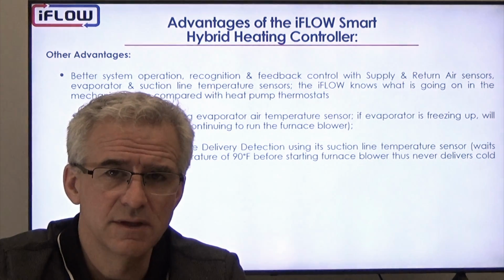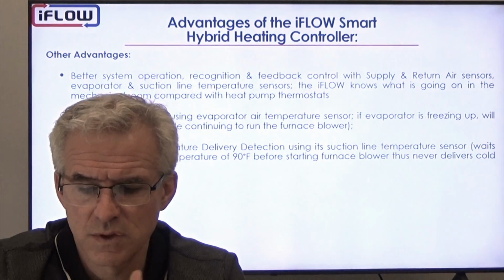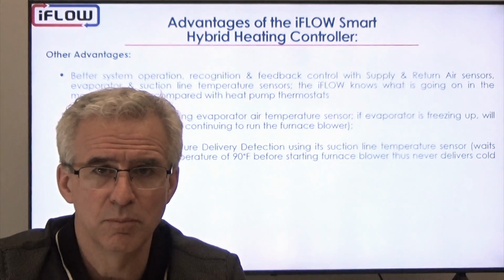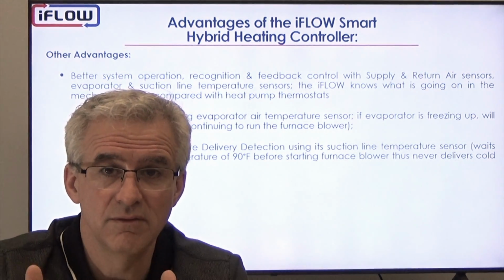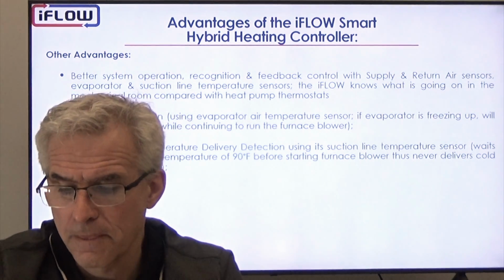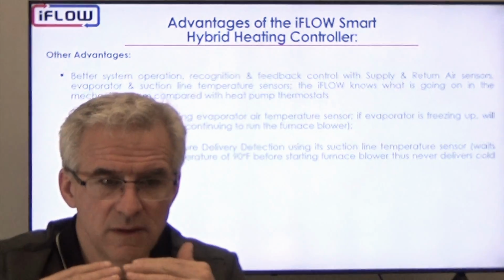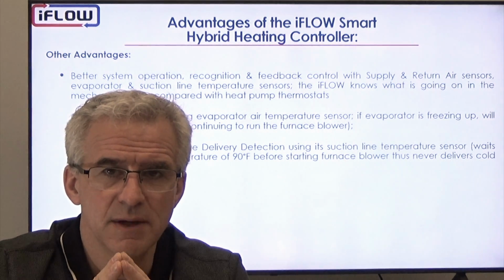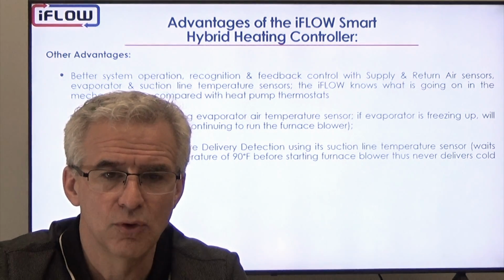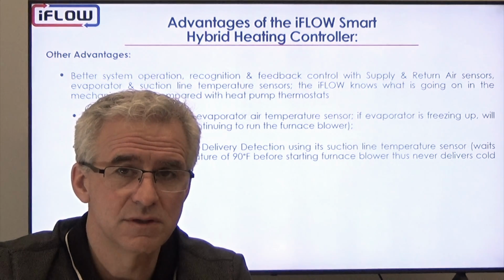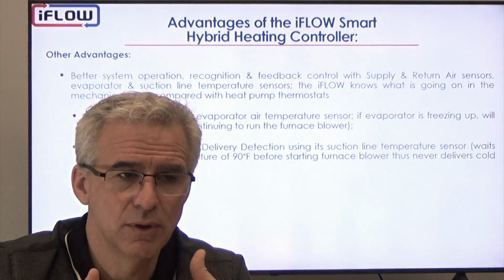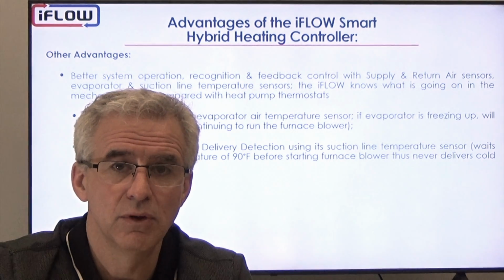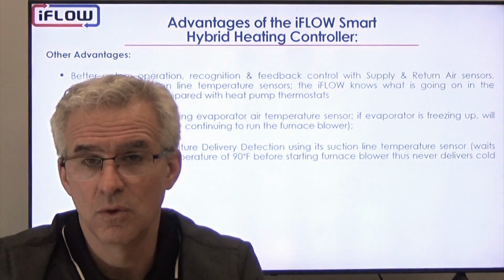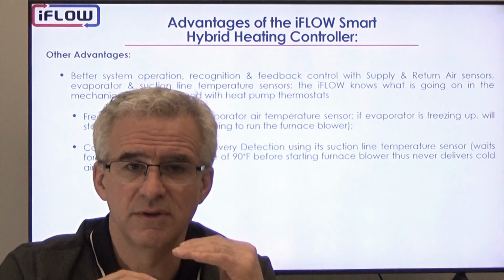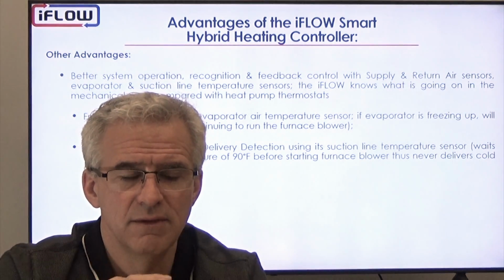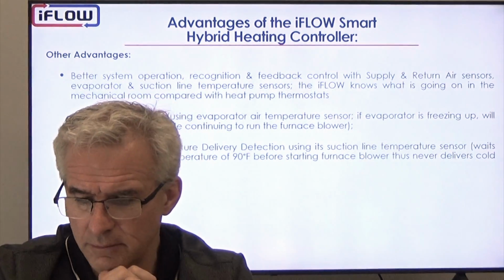We do have another sensor that goes on the suction line, so that is detecting the temperature supplied by the compressor to the evaporator. The suction line sensor is looking for a temperature of 90 degrees Fahrenheit before it allows the blower on the furnace to come on. If we allowed the blower to come on before that, we'd be blowing cold air into the house. So we're actually looking at the performance of the outdoor unit and ensuring that we're getting the temperature we need.